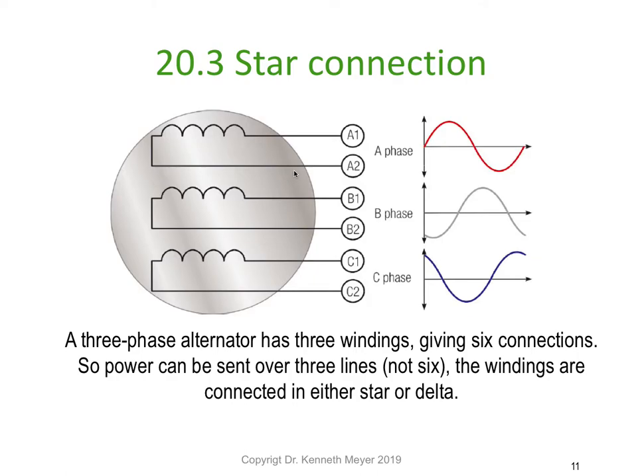Now, star connection properly. You can see the star connection: winding A, winding B, winding C, generating Phase A, then 120 degrees later Phase B, then another 120 degrees — or 240 degrees total — Phase C. We have six winding endings: a start and a finish for each of the three windings. A three-phase alternator has three windings giving six connections, and power can be sent over three lines, not six, by connecting into star or delta.